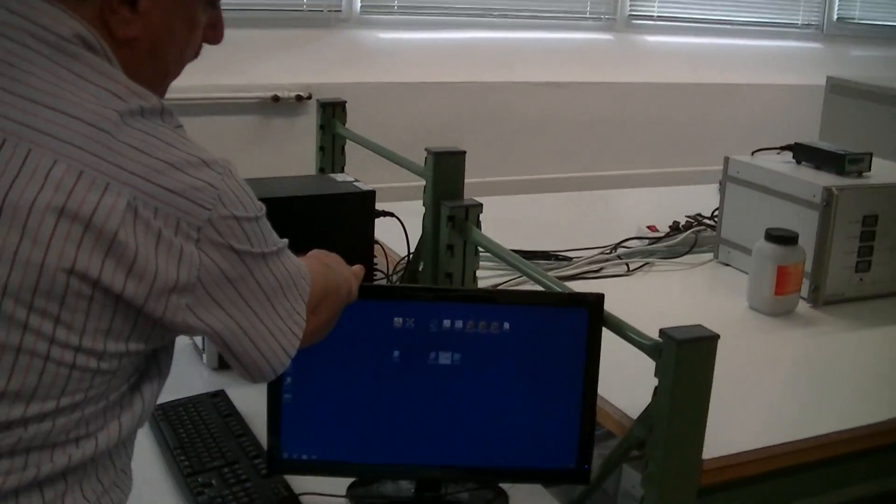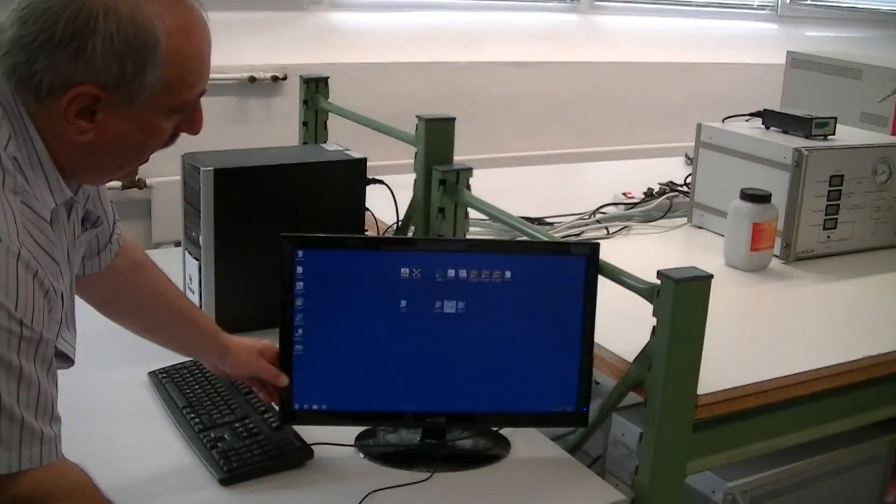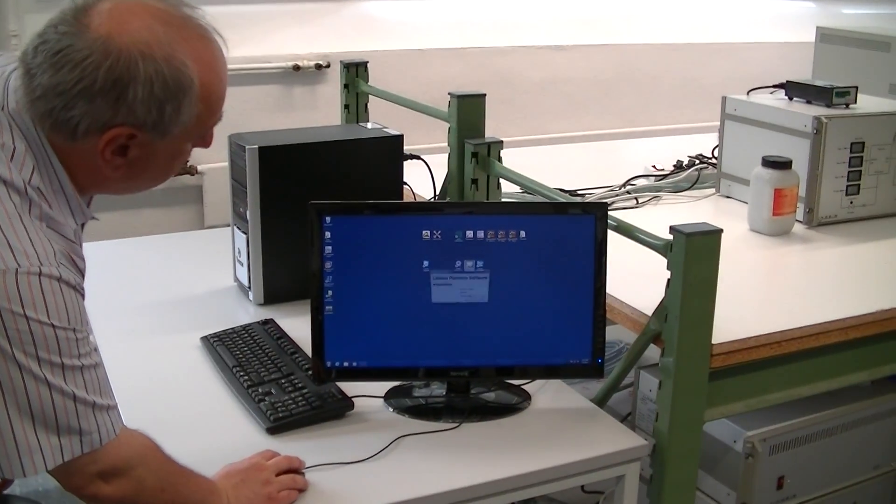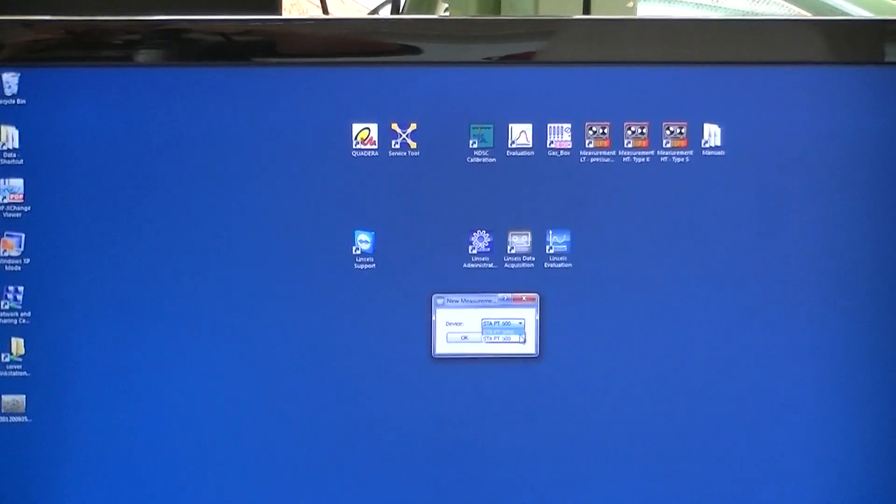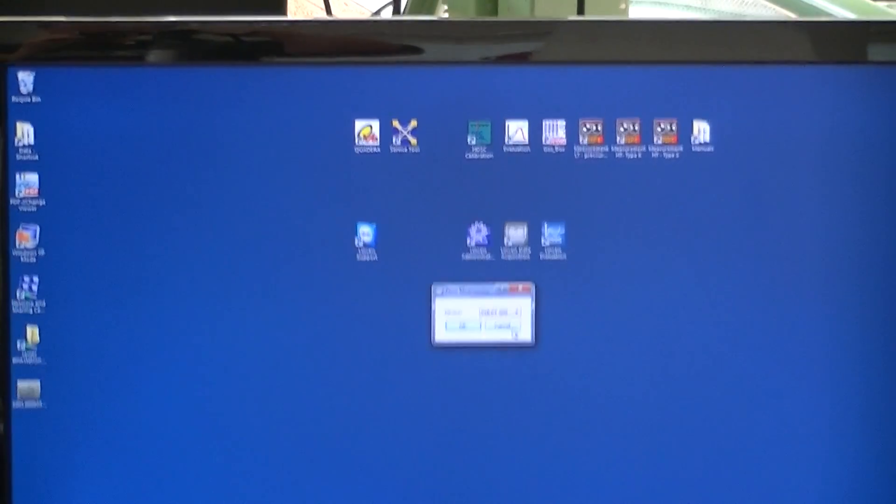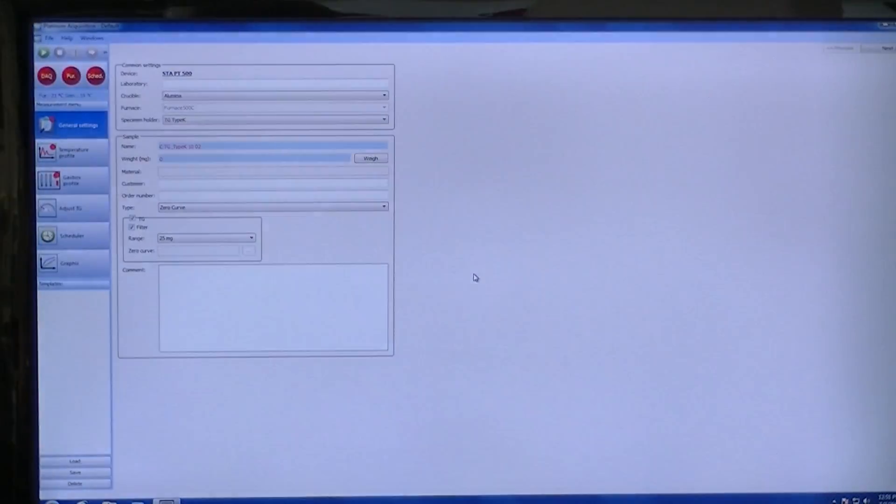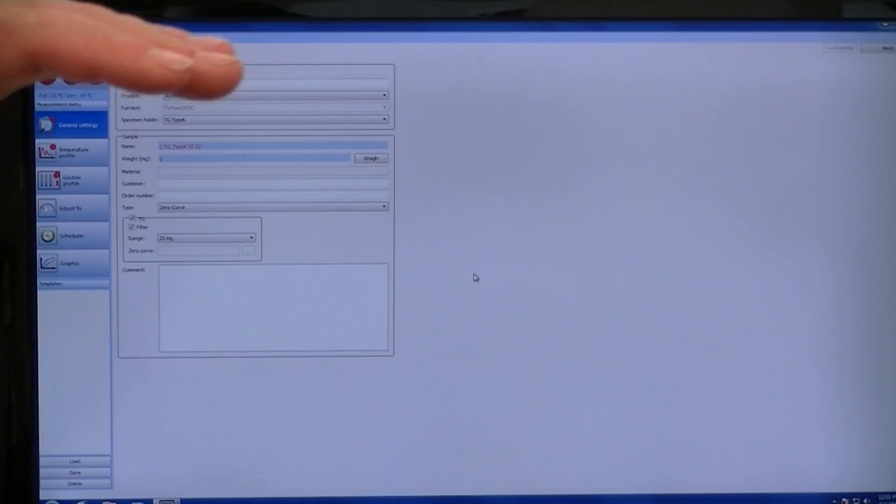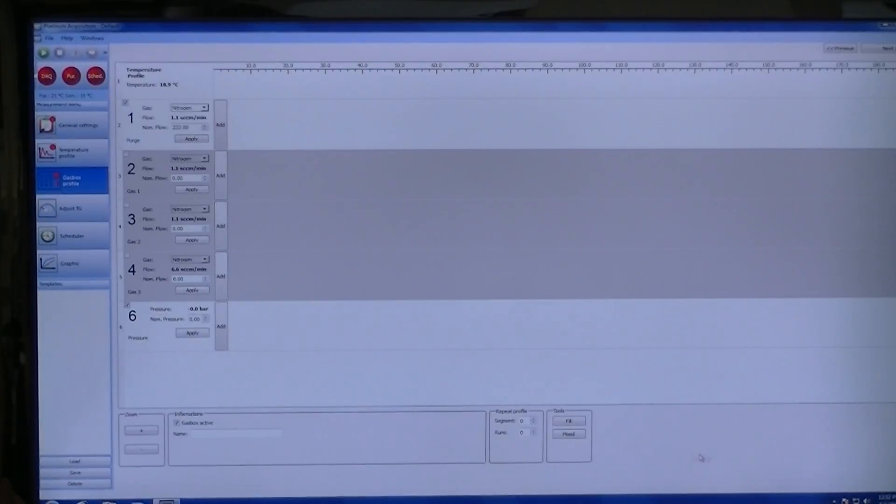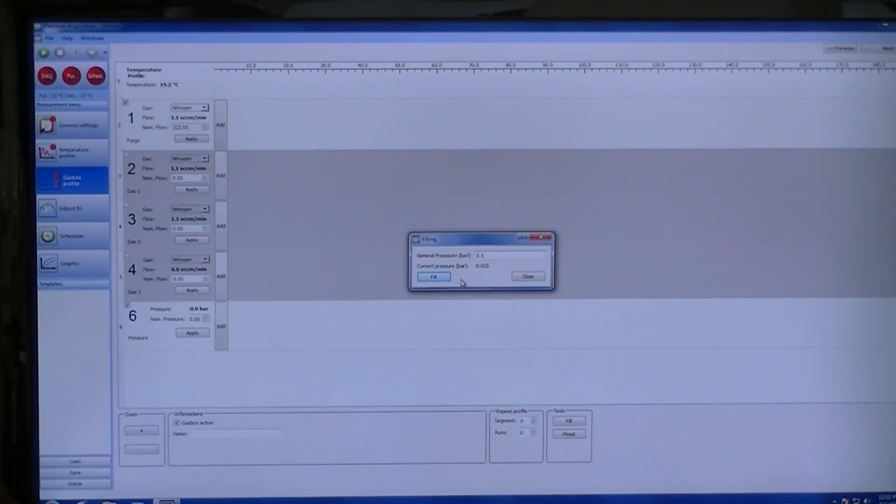For this operation, we have the software here. There's a program called Data Acquisition System. You have to choose which furnace you are working with. The high temperature or the low temperature. The low temperature, 500 Celsius, is with pressure. The high temperature is usually without pressure and can only run between vacuum and a small overpressure maximum one bar. In this software, we have a gas control system. And there's a button which is called Fill. And here we can adjust any pressure. Let's say 0.5 bar and then we can fill the system with this pressure.